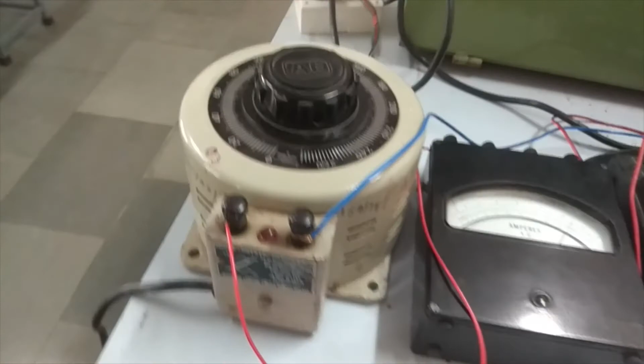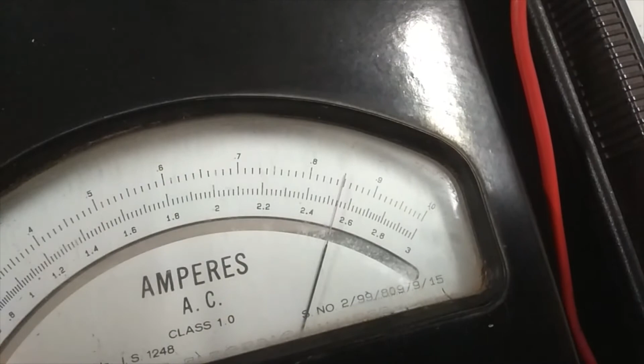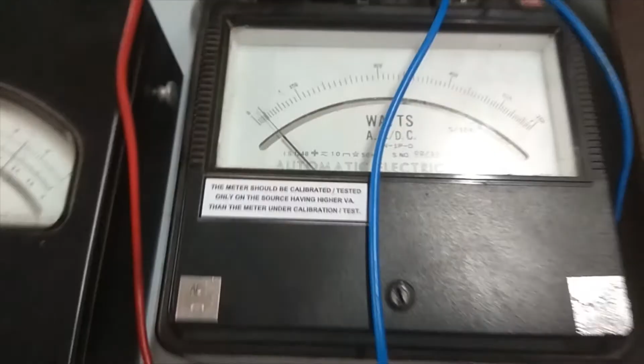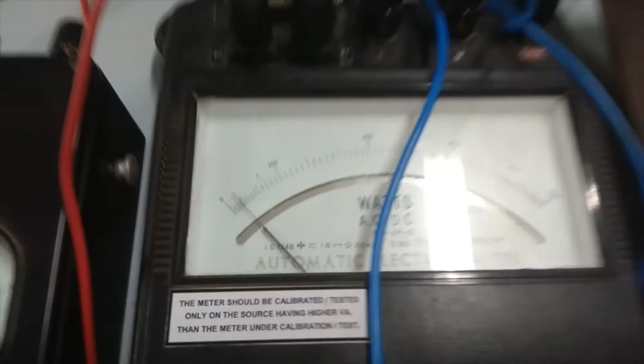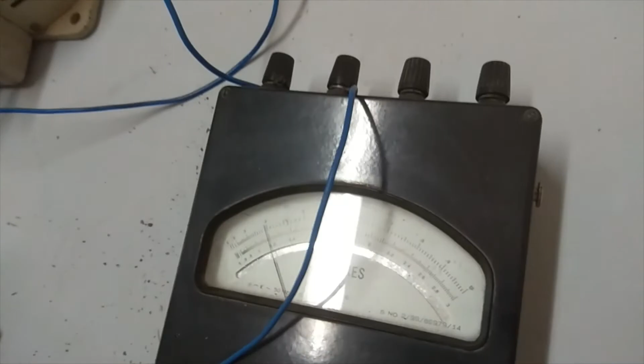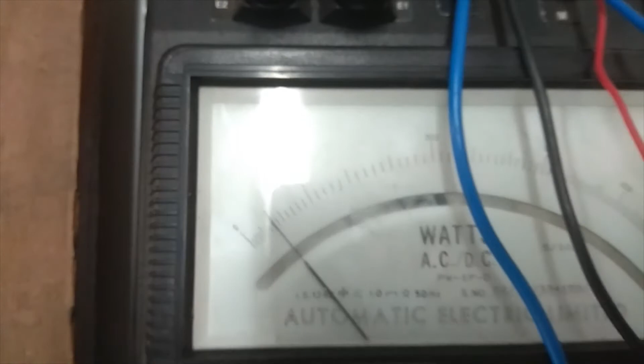So first we are going to note down the readings for the primary side. The primary voltage is 115 volt, which we have measured. Then the current on the primary side, which we can measure from this ammeter, is coming 0.85. And then this primary side wattmeter is going to give us the core loss, or constant losses, and it is coming 40 watt, that we can see. Then we are going to note down the readings of the secondary side. The ammeter gives the secondary current, and it is 4 ampere. The voltage we have seen is 23 volt approximately, and the wattmeter reading here is 80 watt. This wattmeter is going to give the copper losses, and the wattmeter connected on the primary side is giving you core losses.